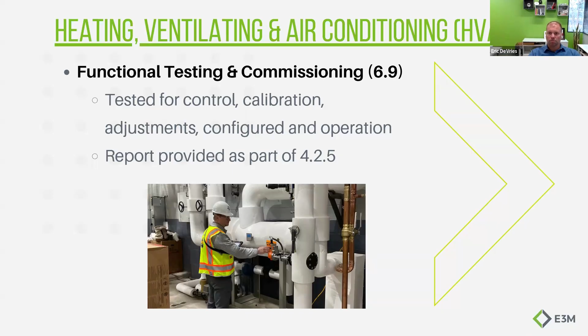I'm going to get back on my drum here a little bit. Functional performance testing. This is required now for any HVAC project. So if you do a full-scale building, you've got to functionally test the controls, calibration of the units, all of that. But if you just do a boiler replacement project, you still have to do a scaled back functional performance test of just the boilers, right? You don't have to get into the existing systems. If you didn't touch the pumps, you don't have to touch anything existing. But if you replace equipment, you've got to have a plan to performance test that to make sure it's running the way it's supposed to.